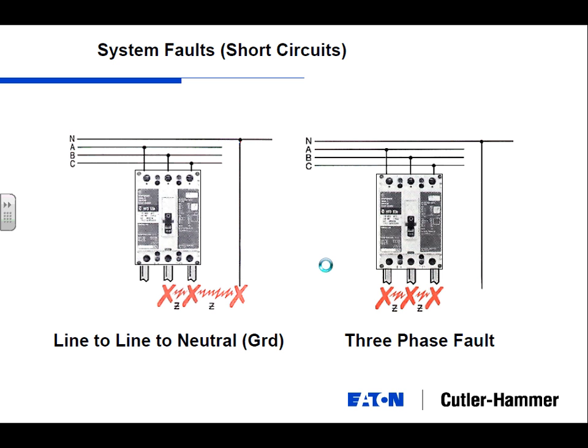When you talk about the most dangerous situation, what is going to be the most dangerous situation? It's going to be three-phase fault. They call it the bolted fault, and that is the worst-case scenario when we talk about how UL dictates in NEC that we need to build our equipment and that the people we're working on the equipment need to be protected. Everything relates to the worst-case scenario, which is the three-phase fault. How often does that happen in real life? Not that often, believe it or not.